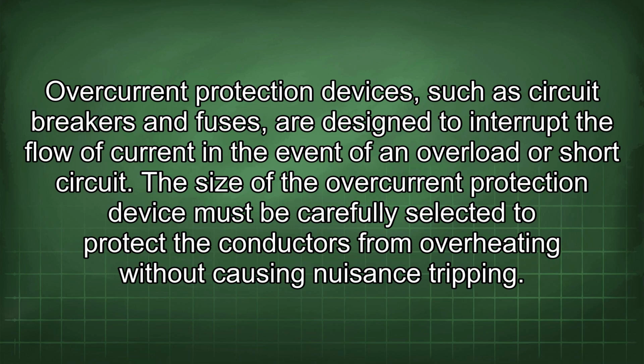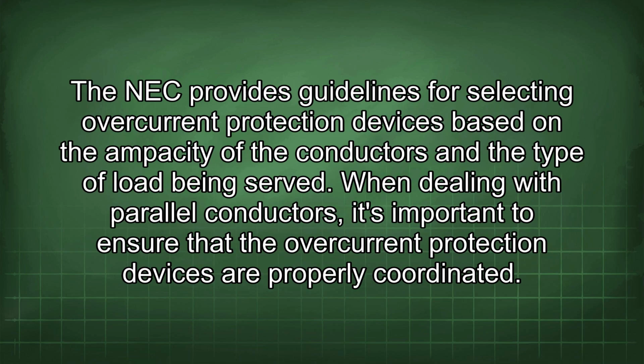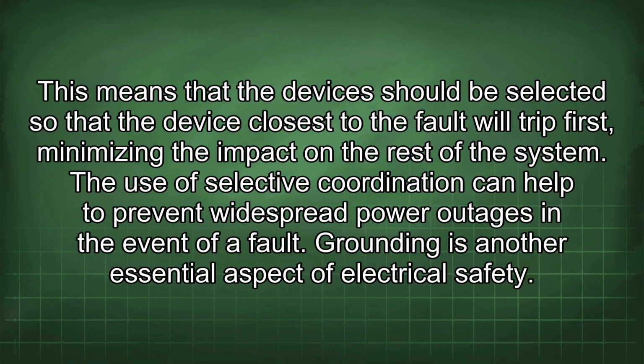The size of the overcurrent protection device must be carefully selected to protect the conductors from overheating without causing nuisance tripping. The NEC provides guidelines for selecting overcurrent protection devices based on the ampacity of the conductors and the type of load being served. When dealing with parallel conductors, it's important to ensure that the overcurrent protection devices are properly coordinated. This means that the devices should be selected so that the device closest to the fault will trip first, minimizing the impact on the rest of the system. The use of selective coordination can help to prevent widespread power outages in the event of a fault.